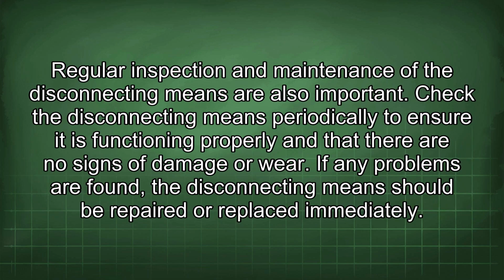Regular inspection and maintenance of the disconnecting means are also important. Check the disconnecting means periodically to ensure it is functioning properly and that there are no signs of damage or wear. If any problems are found, the disconnecting means should be repaired or replaced immediately.